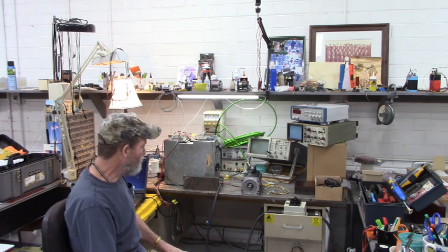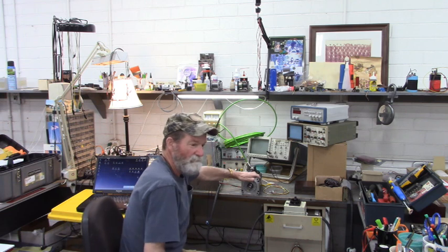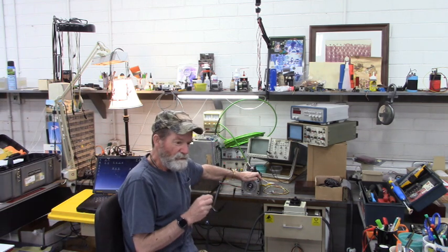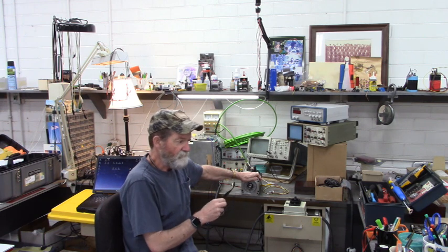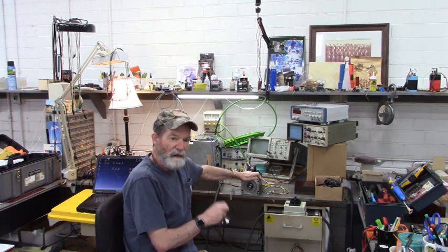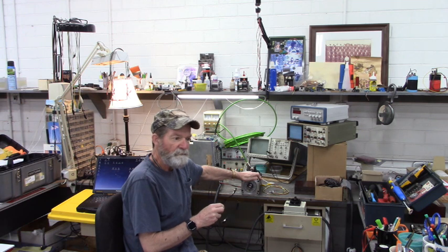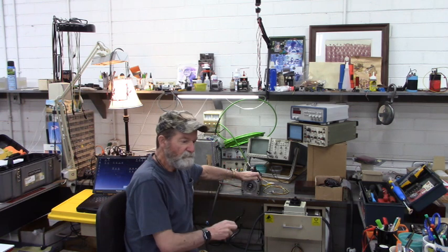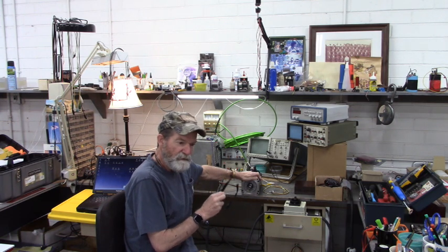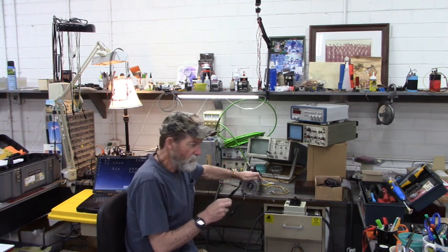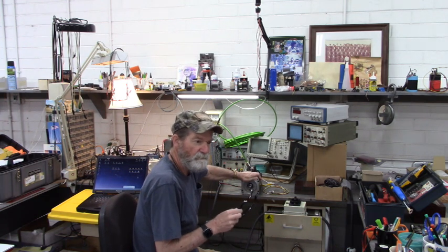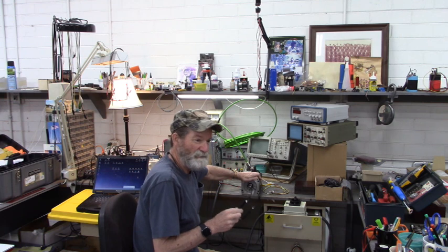Today we are going to be researchers. So what I want to know with this Indramat motor is, if I ever had to change the feedback, because it's a feedback that's timed to the windings of the motor, if there was a way that I could replace that feedback and get it properly timed to the windings of the motor. So we're going to try and figure out a way to do that today. We're going into unknown territory.